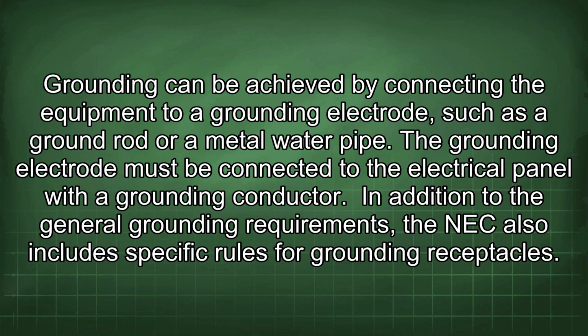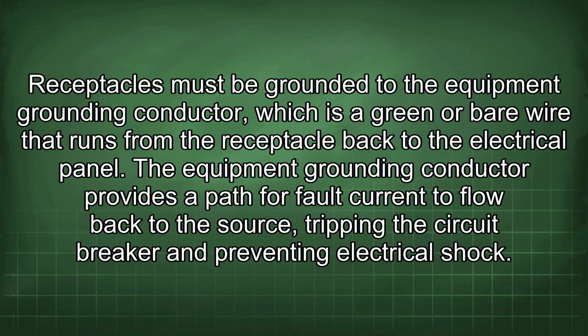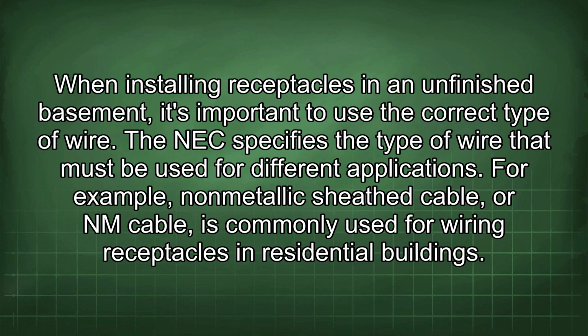In addition to the general grounding requirements, the NEC also includes specific rules for grounding receptacles. Receptacles must be grounded to the equipment grounding conductor, which is a green or bare wire that runs from the receptacle back to the electrical panel. The equipment grounding conductor provides a path for fault current to flow back to the source, tripping the circuit breaker and preventing electrical shock. When installing receptacles in an unfinished basement, it's important to use the correct type of wire.